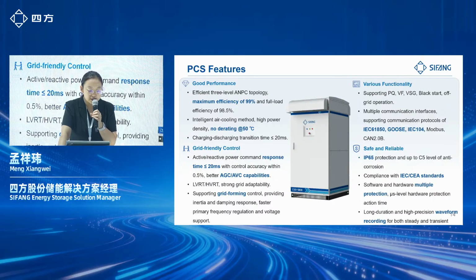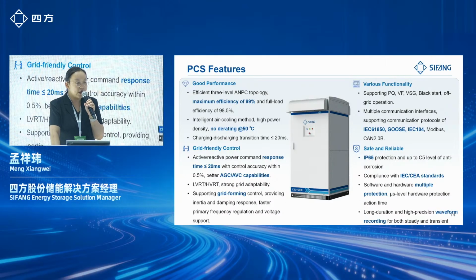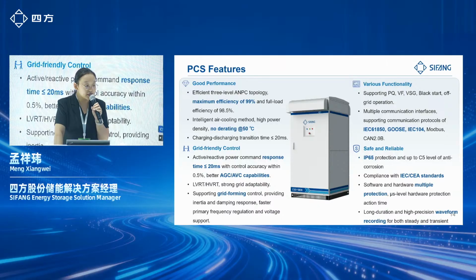We also adopt the intelligent forced air cooling method, which leads to high power density and a small footprint. We obtain full load operating capability at 50 centigrade, with no derating at 50 centigrade. Our PCS has a high protection level of IP65 and a maximum C5 anti-corrosion level. We also adopt multi-level software and hardware protection.